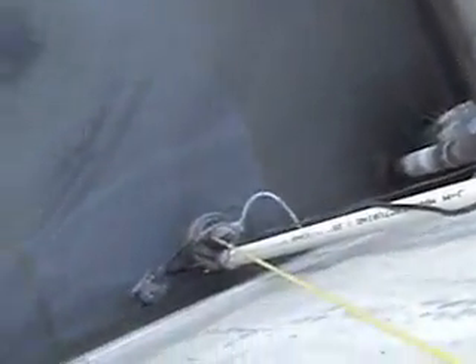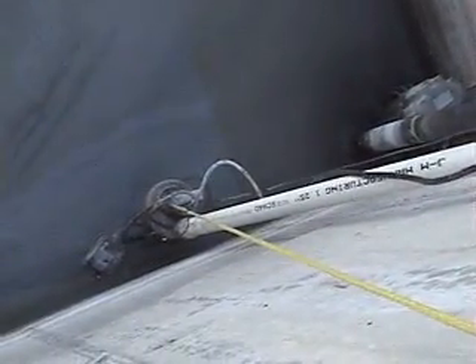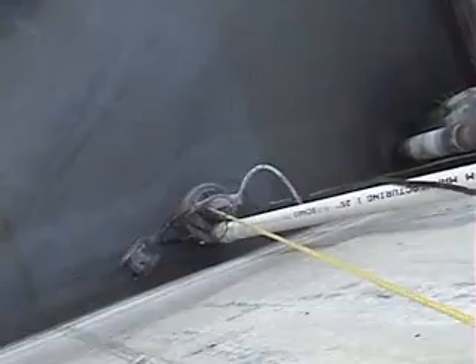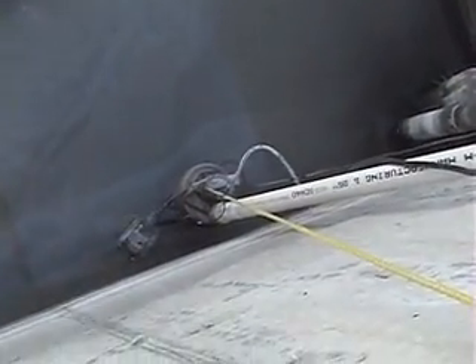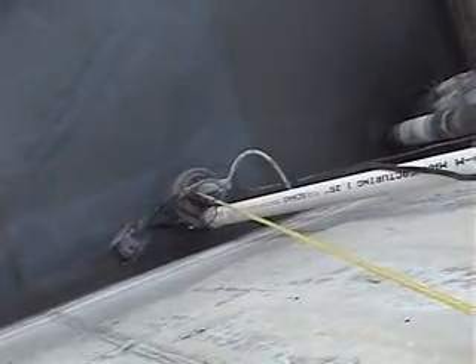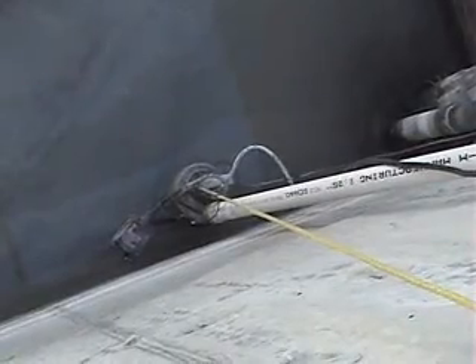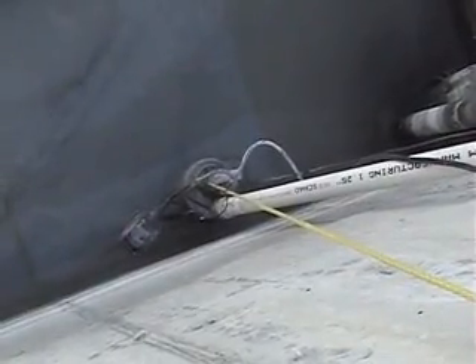As stated before, behind us here is the actual sediment basin and treatment pit. If we look down at the bottom here, we have our submersible pump with float switch, and right next to that is the pH probe. Now, the pH probe simply sits in the sediment basin and picks up the pH 24 hours a day, 7 days a week at all times.